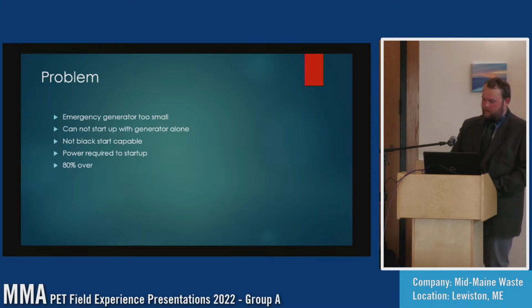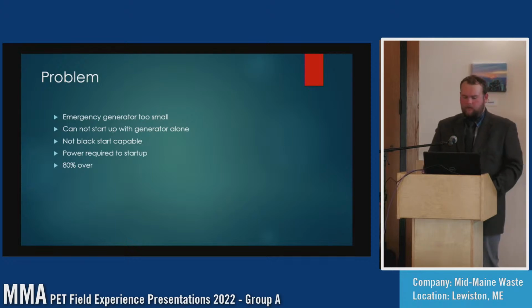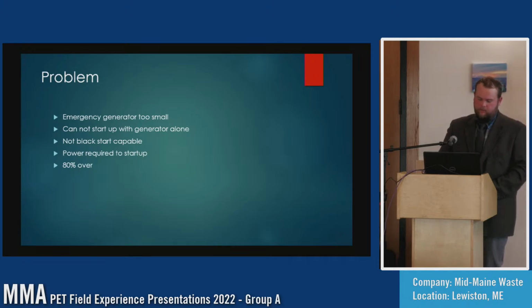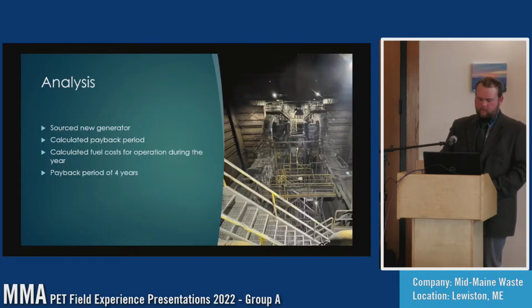And for the power required, I had to go around the plant and get nameplate data off all the equipment and the motors that were required for starting up the boilers. Then I took that number and calculated over 80% of the power just to ensure that the generator was big enough to start the plant up. For my analysis, I sourced a new generator and got that price. I calculated a payback period, taking into consideration power prices and the number of times the plant tripped and went black.